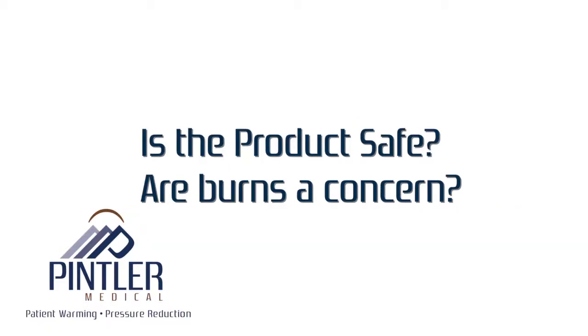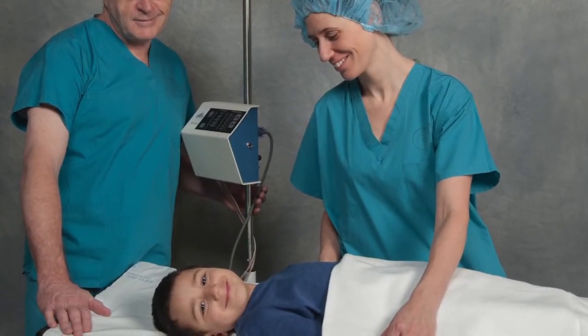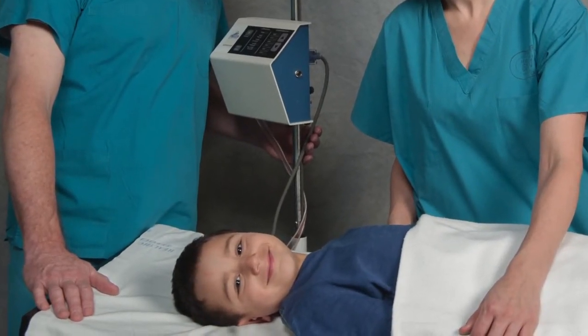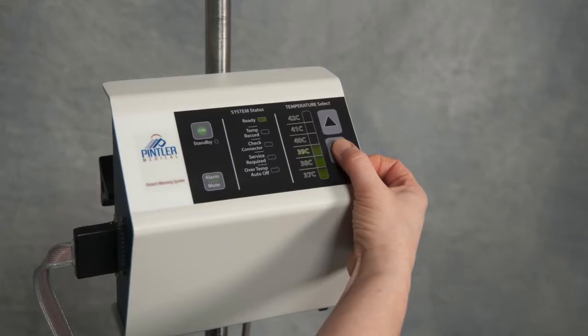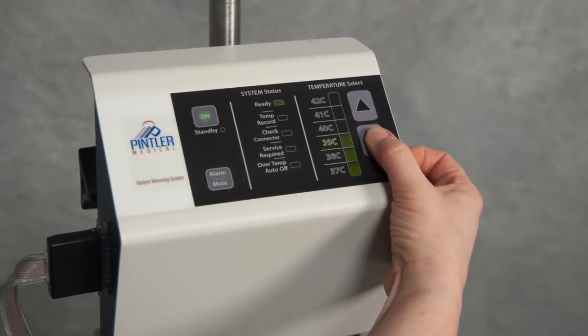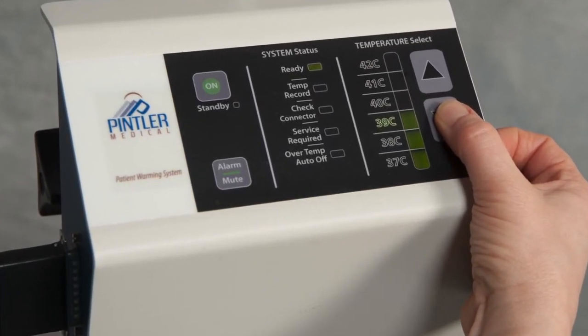Is the product safe? Are patient or staff burns a concern? Years of development and hundreds of thousands of procedures with the original design, and no adverse event has been reported. As a precaution, the Pintler patient warming system is equipped with an automatic safety power-off with any warming temperature exceeding 42 degrees Celsius.